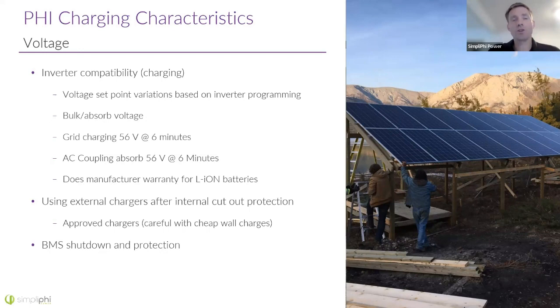So what the charge controller will do is it will hold that voltage constant at 56 volts until the amperage drops to 2% of the battery bank's capacity. So if you had 150 amp hour battery bank capacity, you would set it to 2% of that, which would be 3 amps. So once we're at 56 volts and the amperage keeps coming down and down and down, and once it hits 3 amps, it can cut it off there. So either use that 2% end amps rule, or the 56 volts for 6 minutes, a tenth of an hour.